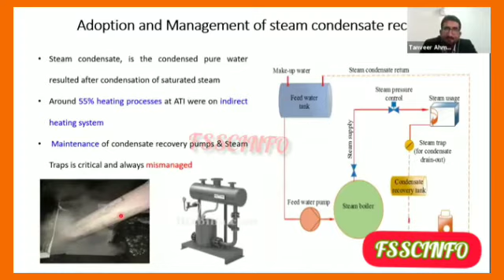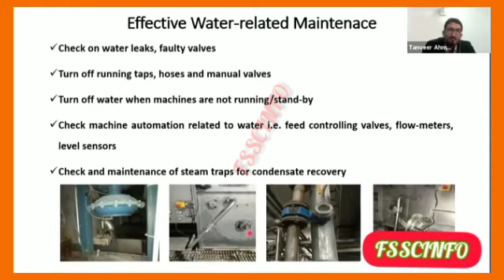Then, water-related maintenance is very important. It is very important to check that water is not being drained directly, that water valves are not manually left open, that we have properly calibrated flow meters, and that we have water controlling valves which control the water intake as per the requirement of the process. With time, they fail, so they need to be monitored and checked on a regular basis to manage the water balance effectively.